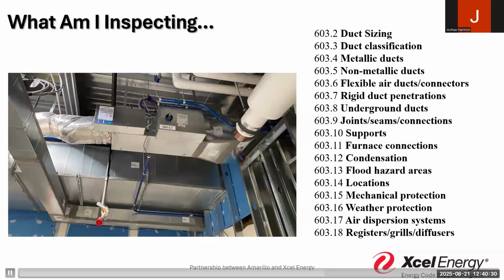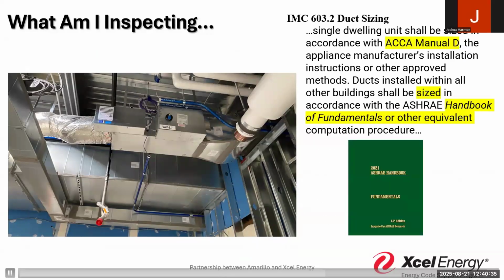Ultimately what both of those codes are driving us towards is recognizing that if we're talking about dwellings in the IMC, we're looking at Manual D. If we're looking at non-dwelling units, we're again going to go back to manufacturers' installation instructions, approved designs, ASHRAE Book of Fundamentals, and other computation systems to determine how much air we're moving through that duct.